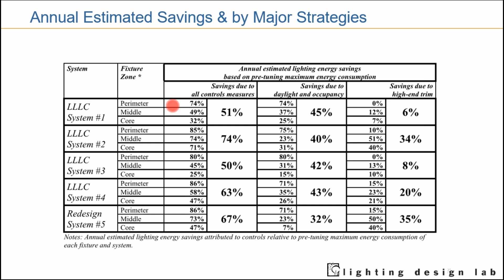What's very interesting is that in terms of savings, all these systems were very comparable. On the right-hand side you can see savings from high-end trim and the differences between daylight and occupancy savings—very comparable numbers across all control strategies. So for a lot less cost and implementation time, the luminaire level lighting control system savings were very comparable, if not better, than the NLC spec and design system.